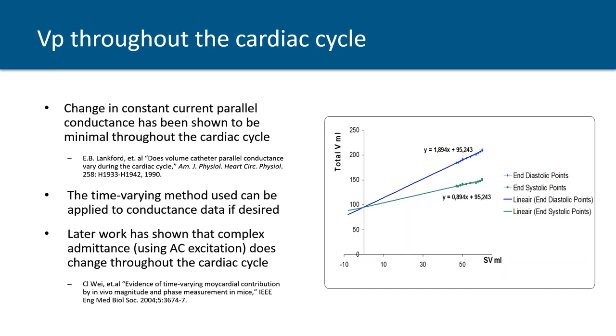And finally, a methodology that is between those two: you can also plot the stroke volume against the total volumes that you measure and regress end diastolic and end systolic volume points. So this is a compromise between the two techniques, and ideally, again, those two points, if the parallel conductance is not changing and you've done a correct wash-in procedure, should intersect at a common point. And again, if you look at the x-axis for the stroke volume, they come back to rendering the stroke volume 0, which again, theoretically renders the blood non-conductive.